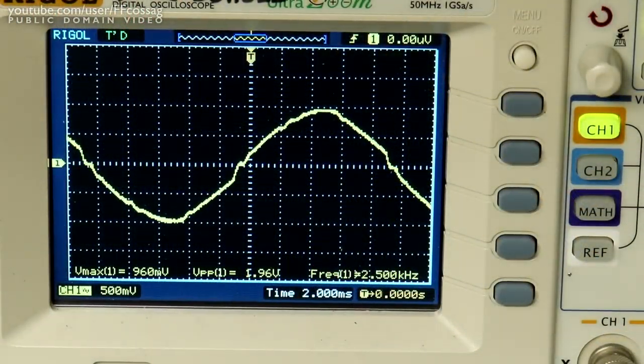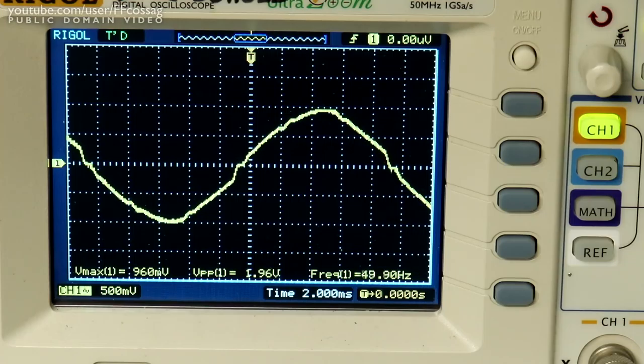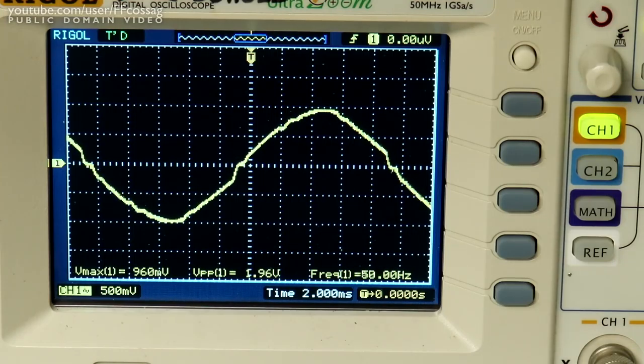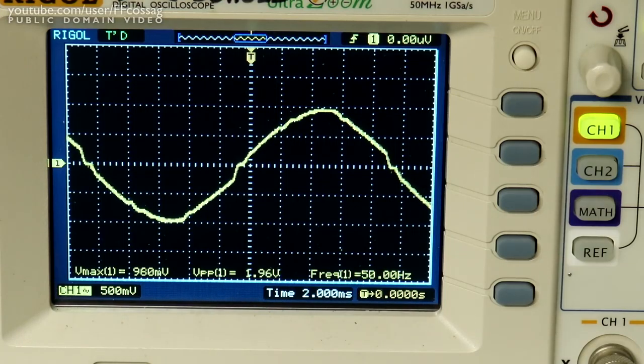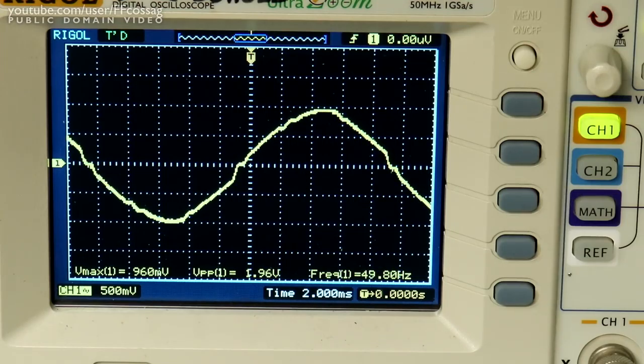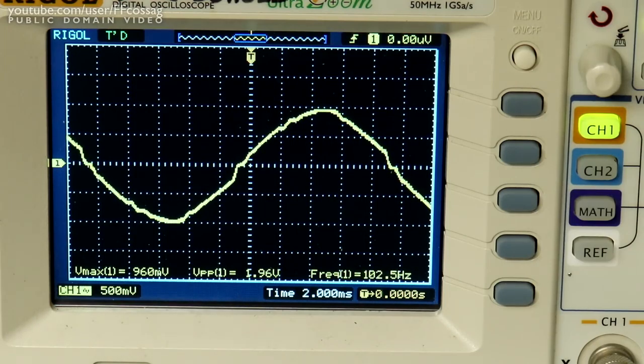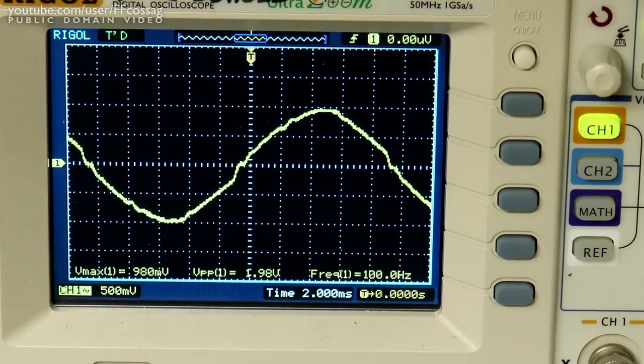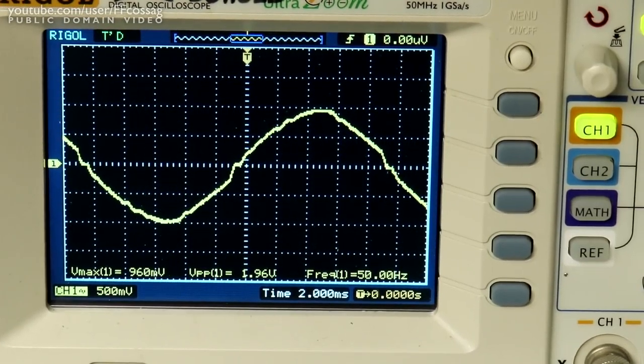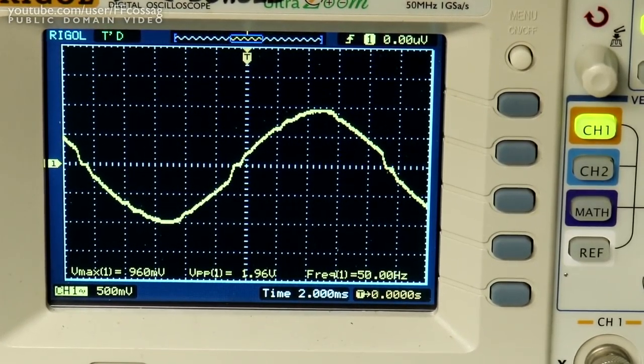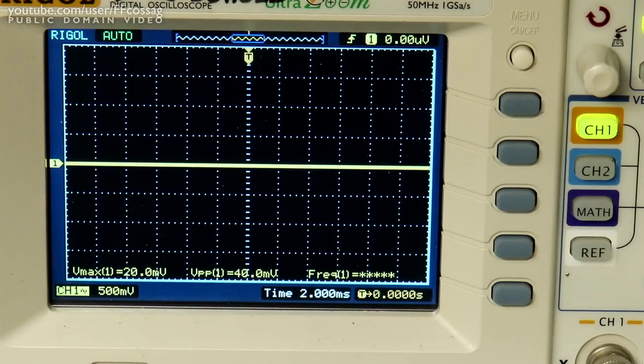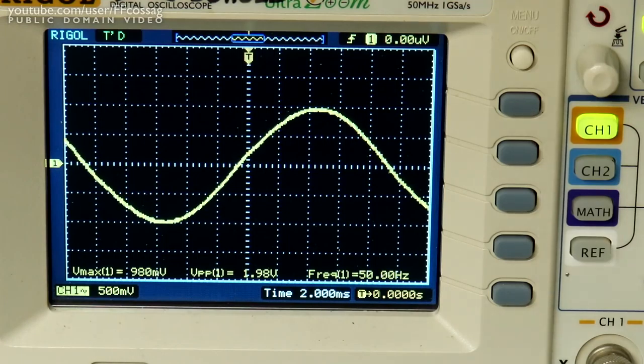I've figured out a way to actually show the distortion on the scope. We're now viewing the power grid as seen through the monitor output of the 339A distortion analyzer. We're just measuring the output voltage. This is what the power grid looks like. Now I'm going to move the transformer from the wall into the output of the UPS. You will notice a considerable change.